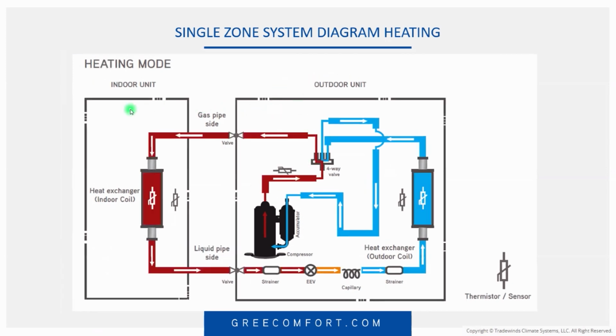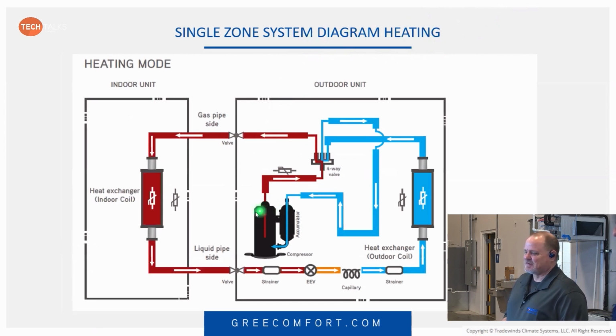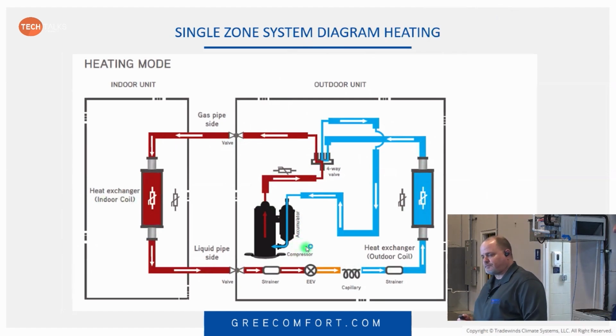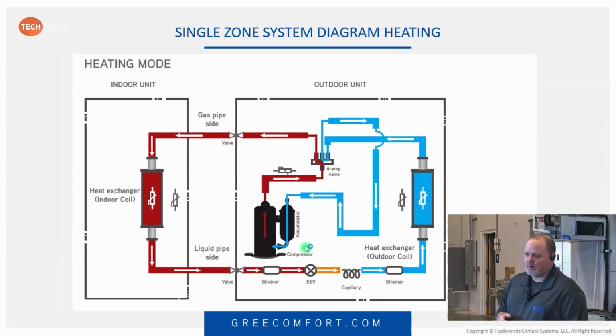You go into heating mode. So we've got two of them in heating mode. That's awesome. So this one we actually named right. Anyway, so discharge off the compressor, going through a reversing valve. It's now switched. We're going to the hot gas inside, releasing the heat to the indoor unit, and we are feeding our liquid back, going through our metering devices, feeding our refrigerant to our outdoor unit, absorbing heat from outside, boiling that gas off. Our suction gas is coming back, going into our compressor. So keep in mind, that's how this machine works.